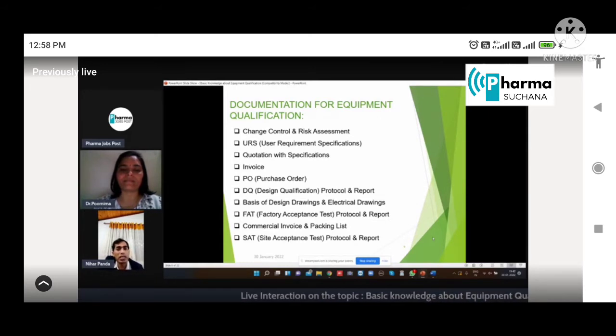Next is SAT, site acceptance test. This is the confusing part of qualification. That's what SAT is. SAT means site acceptance test. We cannot open the equipment before installation because the service engineer should open that equipment and verify the parts, whether they are damaged or not. But in the SAT document, you can check the packing list. What are the items in the packing list? What are the change parts?